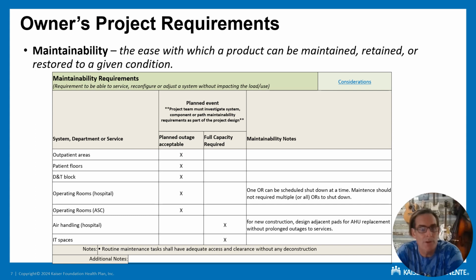For hospital operating rooms, that's a bit of an exception. We do want to be able to maintain central systems without shutting down multiple operating rooms. In the past, we've had systems where in order to work on the air handlers, you had to shut down all the ORs, so we want to avoid that. That doesn't mean, though, that each OR has to be continuously running. We can always schedule a maintenance shutdown for one operating room, but we don't want to shut down the whole block. That's where we get in trouble.